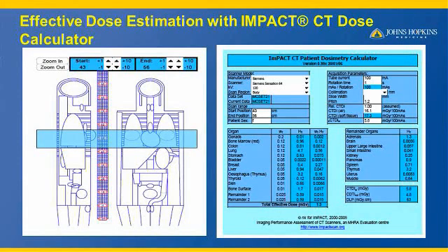There are many methods of estimating the radiation dose in CT. One commonly used method is a computer program which uses anthropomorphic size phantoms — geometric representations of organs — and also has information of the scanner parameters. One can select the region of the scan and the program will output both the organ doses and the effective dose. There are also other methods for calculating radiation dose, such as conversion factors. From the information available at the end of the scan, one can use these easy-to-use conversion factors for estimating effective dose values.